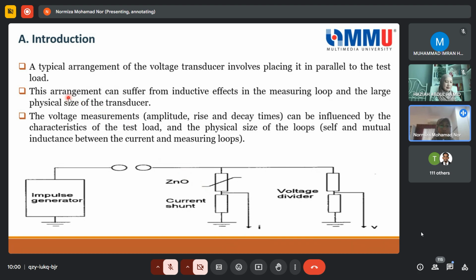Okay, but as we all know as well, this arrangement can suffer from inductive effect in the measuring loop. So when you introduce the loop here, and then the physical size of the transducer, it will have inductive effect. The inductive effect, of course, can cause some delay. Sorry, Dr. Hazia, I do not have my pen here for some reason, so I'll try to draw with my mouse. So you have the delay, whereas the response of the impulse should be a fast response. It means it's sharp here, and then it decays like that. But because of the presence of the inductance, you have this delay here, right?